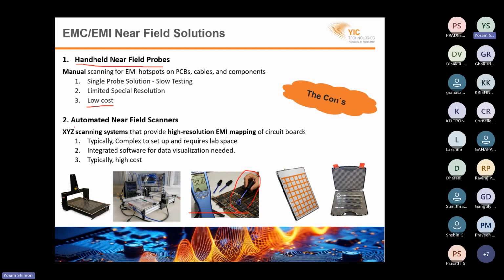The next one is essentially the automated near field scanners, and this is something like that. And this is actually our scanner. The idea behind it, or again, something like that, you can easily build yourself today. The advantage here is that it's a more controlled environment. You can precisely control the near field probes. However, they're a bit more complex to set up. Most likely you will need some kind of integrated software to control it. If you're doing it yourself, it can be done with Python or something similar. And typically it will be higher cost than just a handheld probe, but it will give you better results.